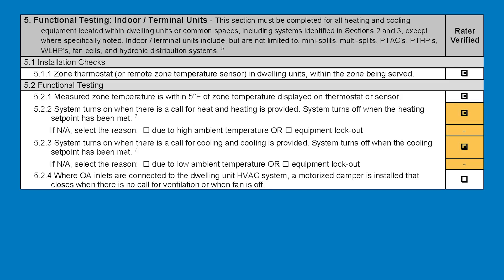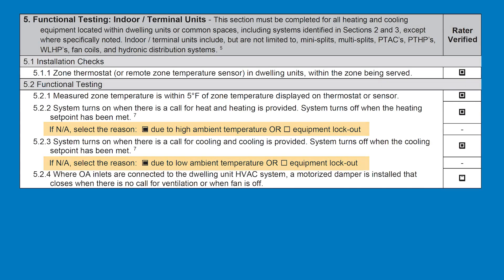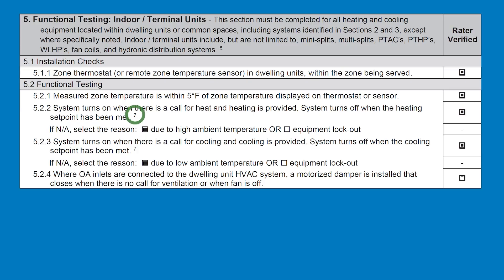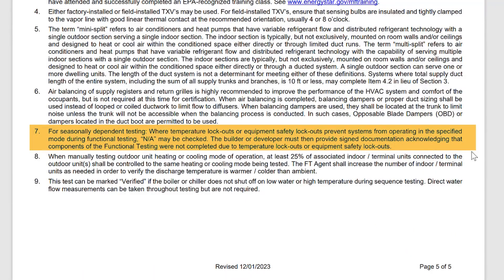When these sections have been completed, mark the appropriate checkbox in the columns on the right. There are some exceptions where someone may mark NA, or not applicable, for certain reasons — such as high or low ambient temperature, or equipment lockout due to ambient temperature. If this is the case, mark the appropriate box, but also confirm that you are getting the builder or developer to provide signed documentation acknowledging the component of the functional testing was not completed due to temperature lockout or equipment safety lockouts.